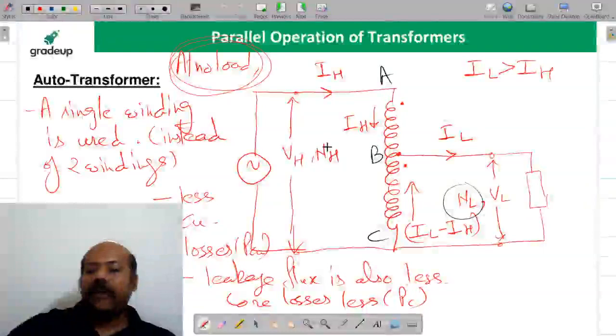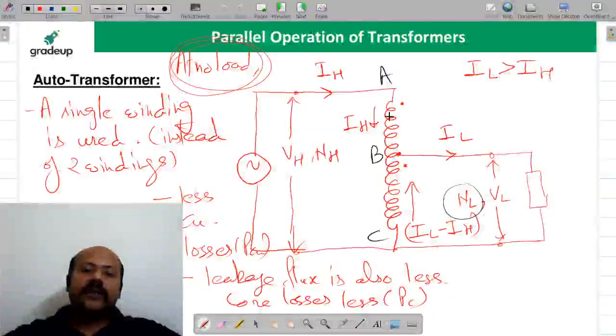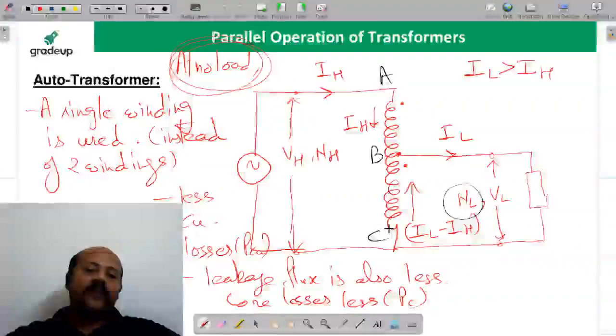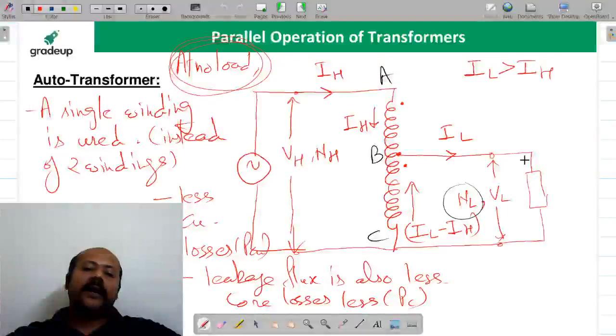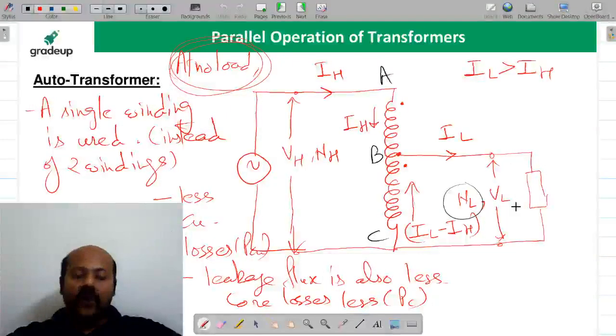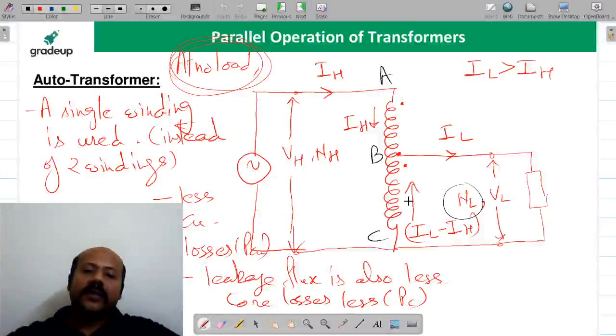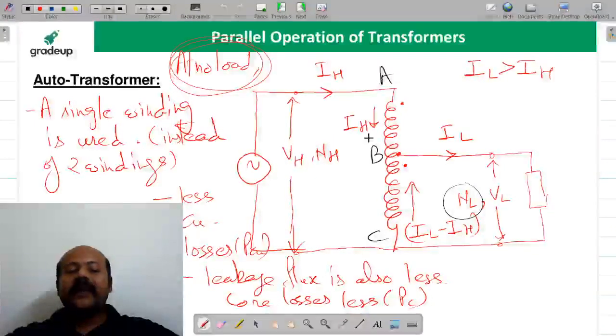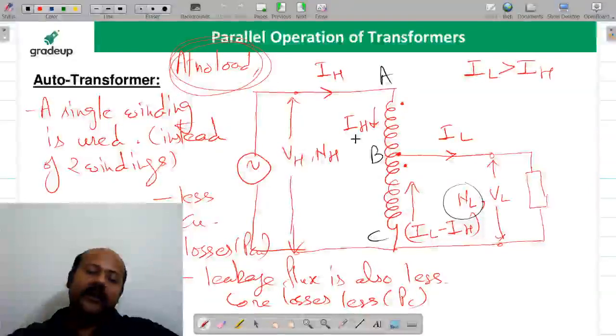If you see this ABC section of the winding, if no load is connected here, and you want to set up a flux in the winding, so you need some current. That current we are calling as the no load current.